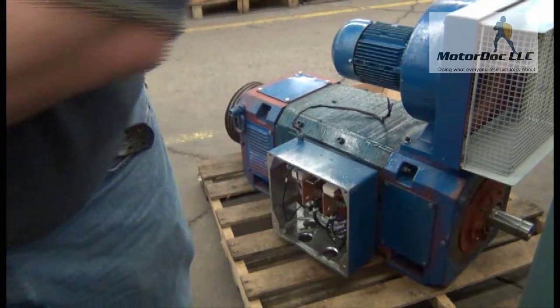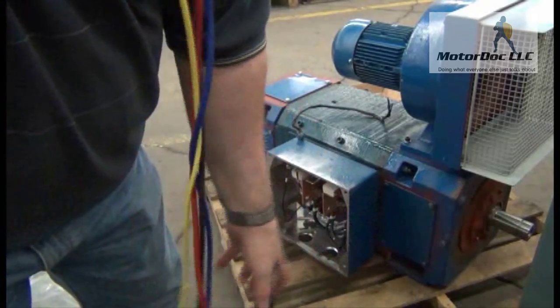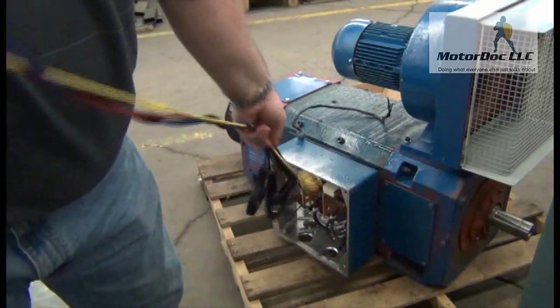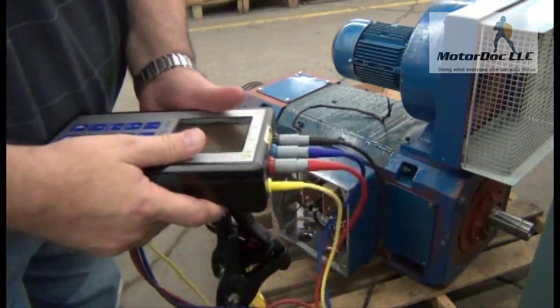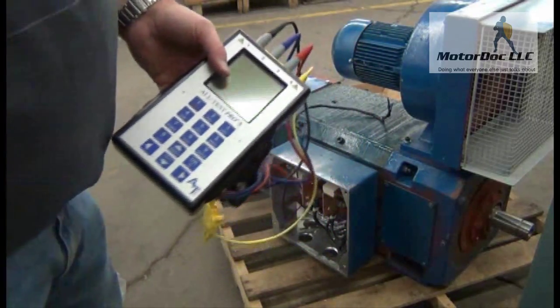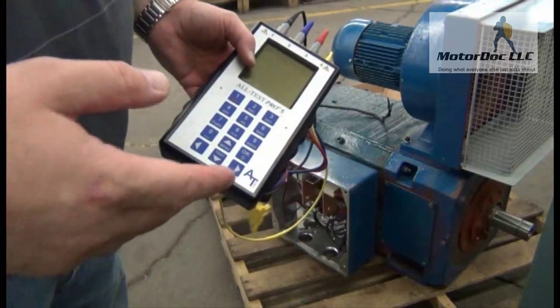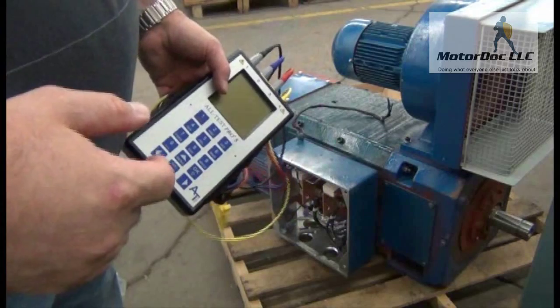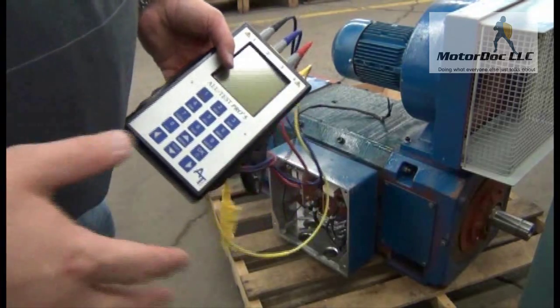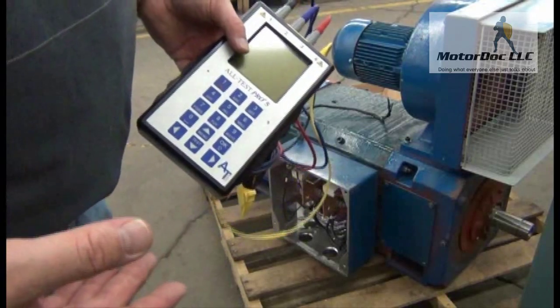Today we're going to test a small DC motor to demonstrate the ALL-TEST PRO 5. This is a single voltage machine and we're going to go ahead and select that. I'm going to show you the single voltage machine for a single test. Then we'll do a special test I use for troubleshooting to see if the armature is contaminated, above and beyond the standard tests.